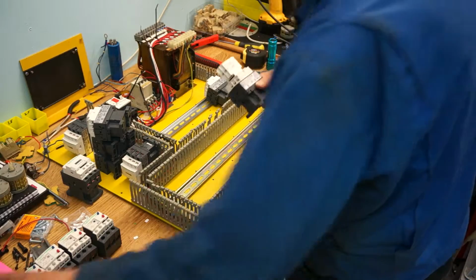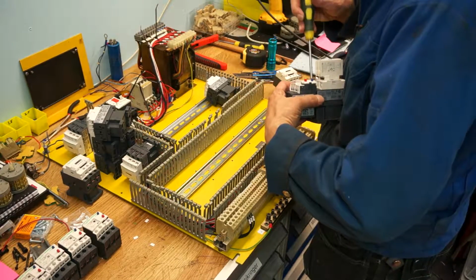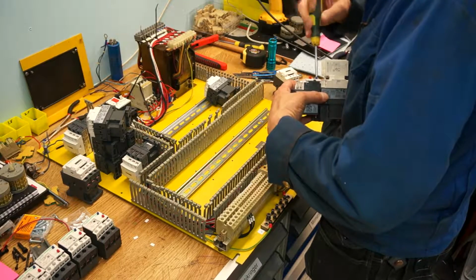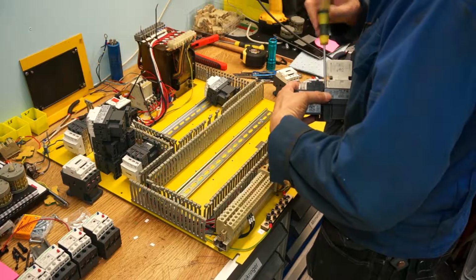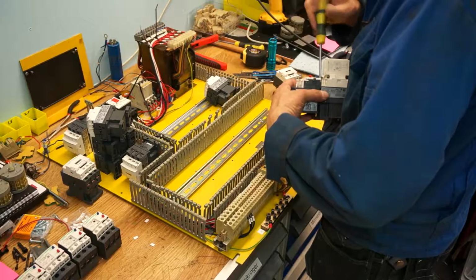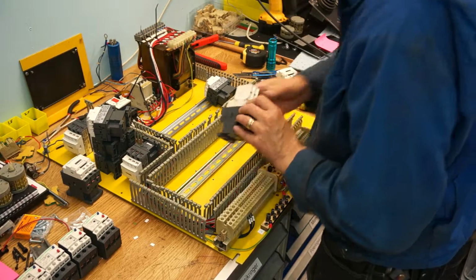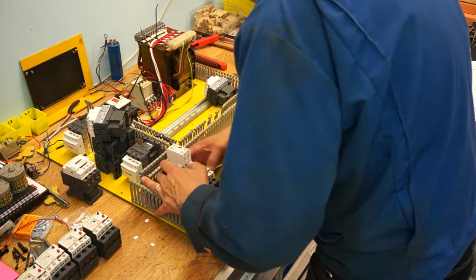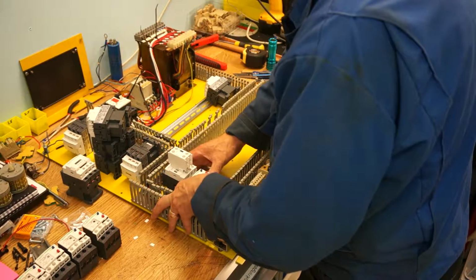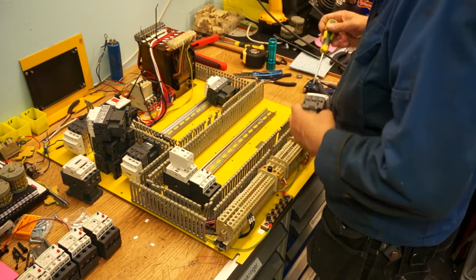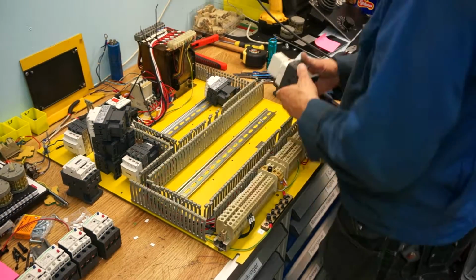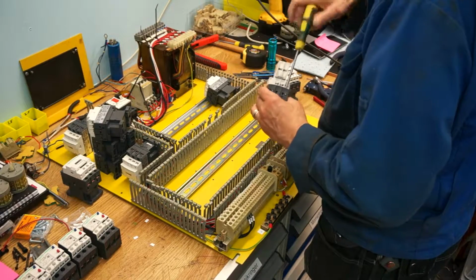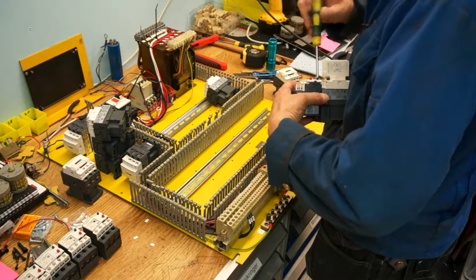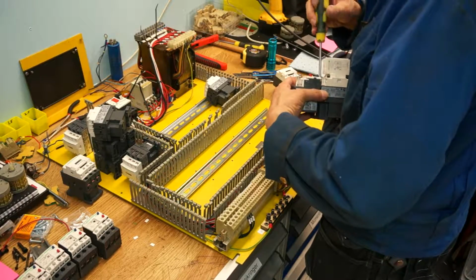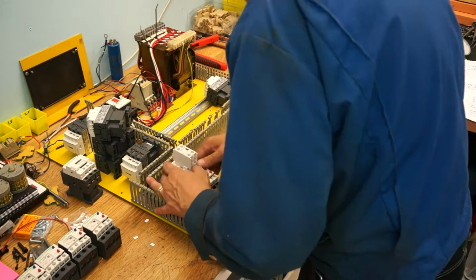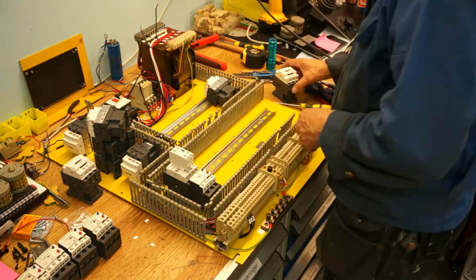The contactors are for switching high power, high voltage. On the first one there, you can see the contactor. It's for three-phase. They rate up to 600 volts, and they're controlled by, in my case, 48 volt DC. That 48 volt is switched by the circuit boards that we'll get to later, with relays. So the relays are actually generating the input signal for the contactor, which in turn switches on or off the three-phase.